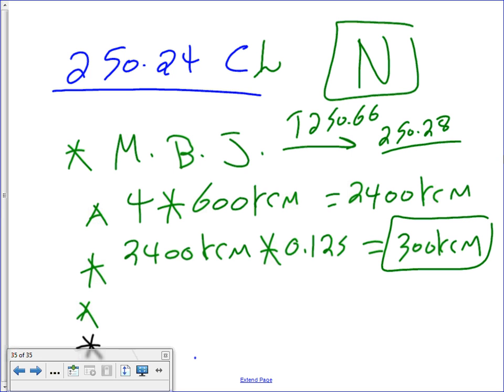Is 300 kcmil a standard size? Yeah, if you go to Chapter 9, Table 8, 300 kcmil is a standard size. So we hit the jackpot. If it wasn't a standard size, what would you do? You go to the next standard. So that's the size of my main bonding jumper.